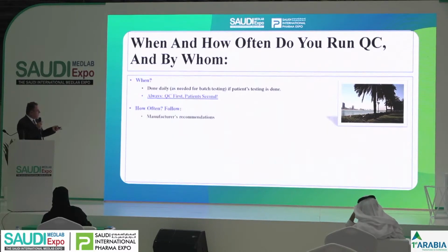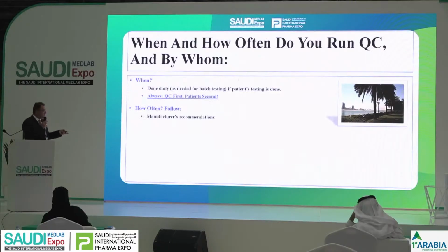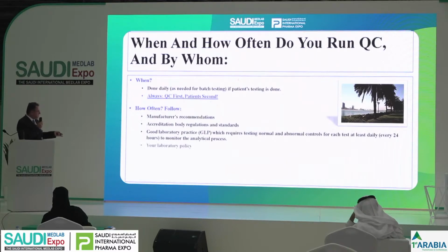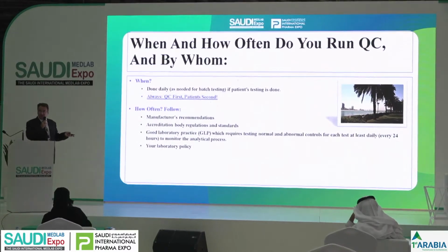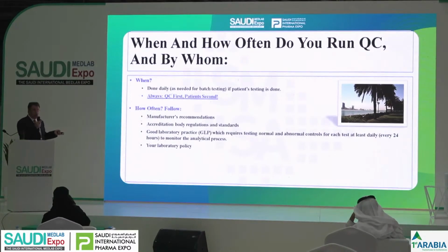How often, you need to follow manufacturer's recommendation. If they tell you do once a day, then you do once a day. Okay, once every shift, then you do once every shift. Okay, and accreditation body regulation and standard, good laboratory practice, or your laboratory policy. But your laboratory policy cannot be less stringent than the accreditation body or the manufacturer recommendation.